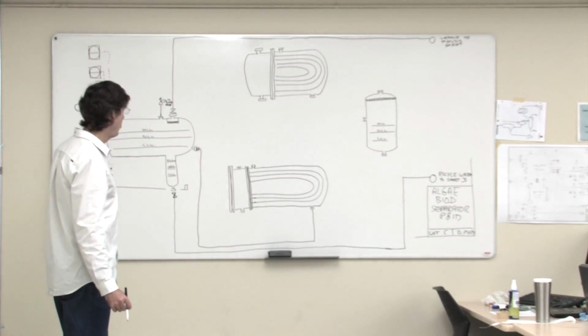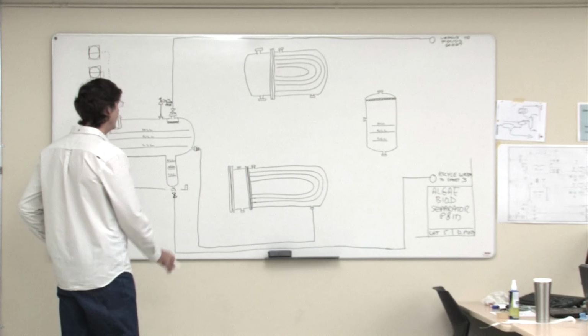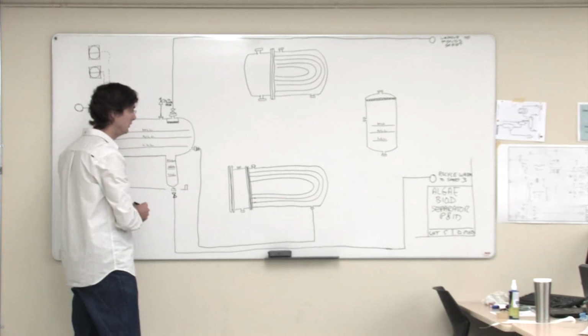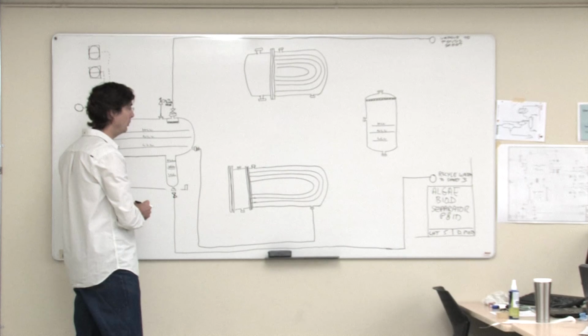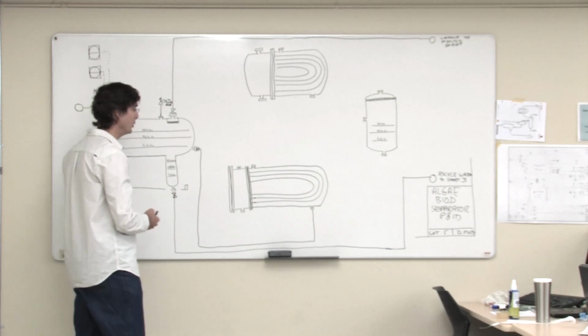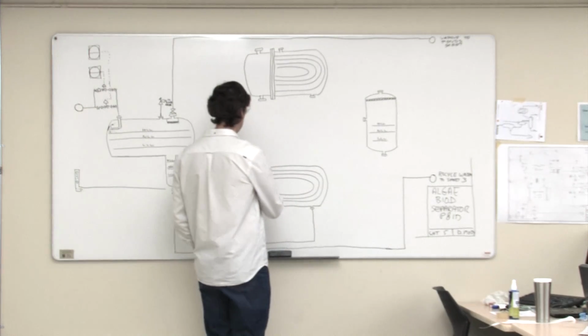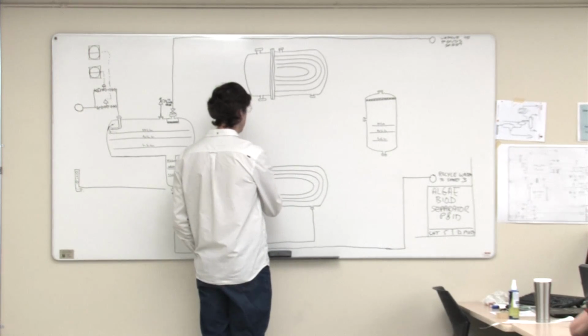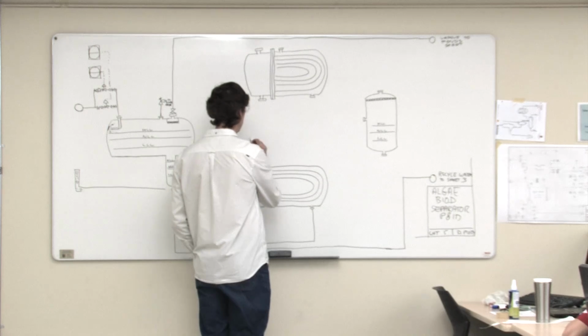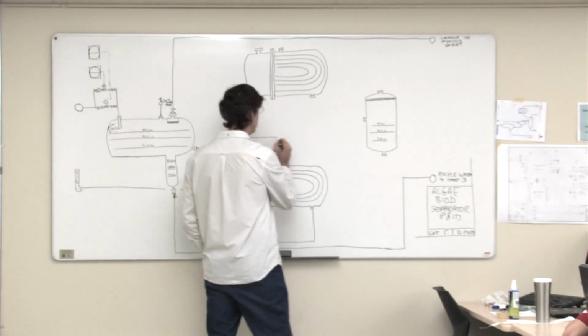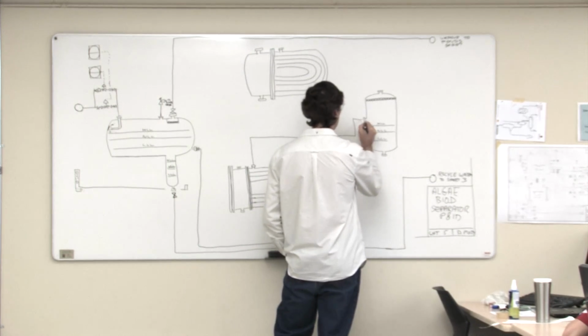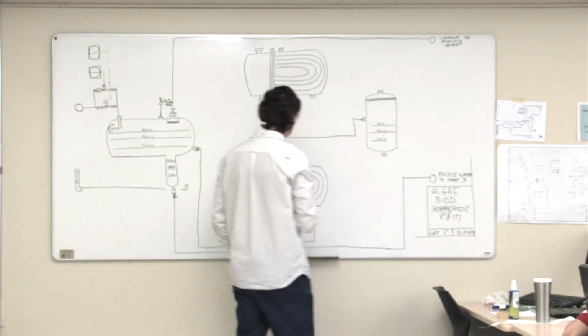Do you have any particular guidelines for when you would not want to? I'd say the general rule is to put isolation on stuff. If you really want to avoid putting a relief valve in, then you need to get rid of the isolation valve. Let me draw this up here. I might rethink it. As I'm doing stuff, I sometimes rethink and go back and put isolation valves in.